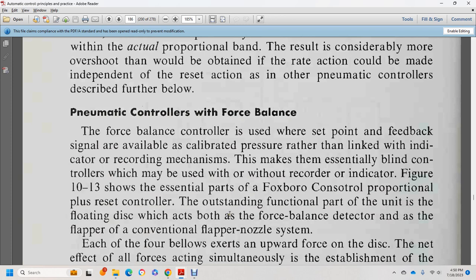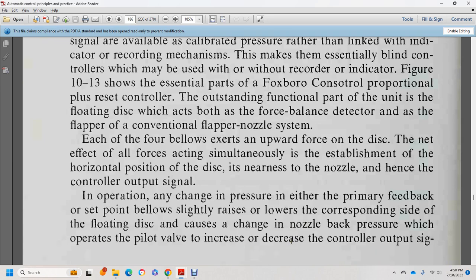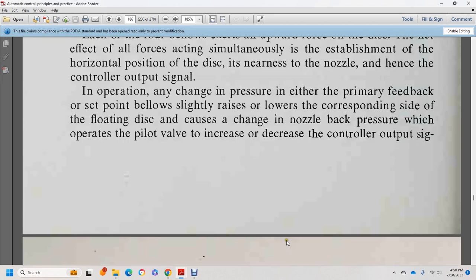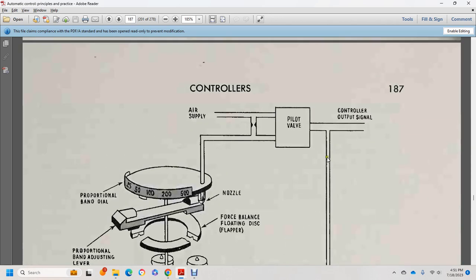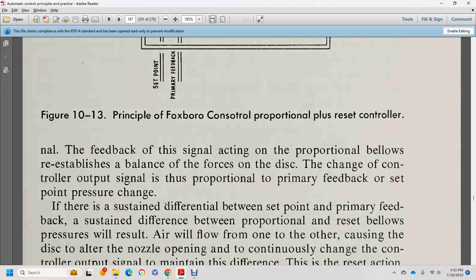Pneumatic force balance control uses set point and feedback bellows calibrated by pressure rather than length, making them essentially blind — suitable for control without a recorder or indicator. Figure 10-13 shows the essential parts of the proportional plus reset force balance controller. The outstanding component is a floating disc, which acts as a flapper in a conventional flapper-nozzle system. Each of the four bellows exerts a force on the disc, with the net effect establishing the horizontal position of the disc nearest to the nozzle.